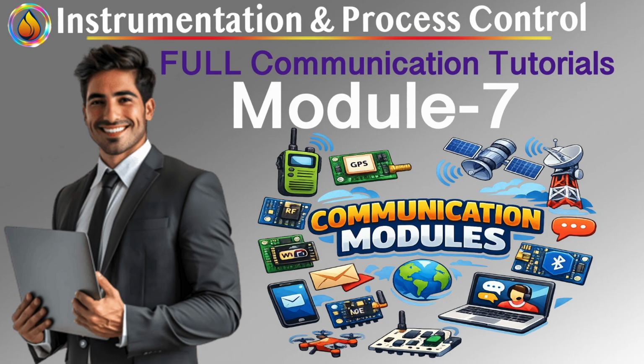Scheduled versus unscheduled communication. Foundation Fieldbus separates traffic into two worlds: scheduled cyclic communication, meaning process data, control loop variables, and time-critical information; and unscheduled acyclic communication, meaning configuration, diagnostics, and maintenance access. The latter never interferes with the former. Scheduled traffic always gets its slot. Acyclic traffic fills the gaps, never the other way around. That ordering is why FF remains calm under load.